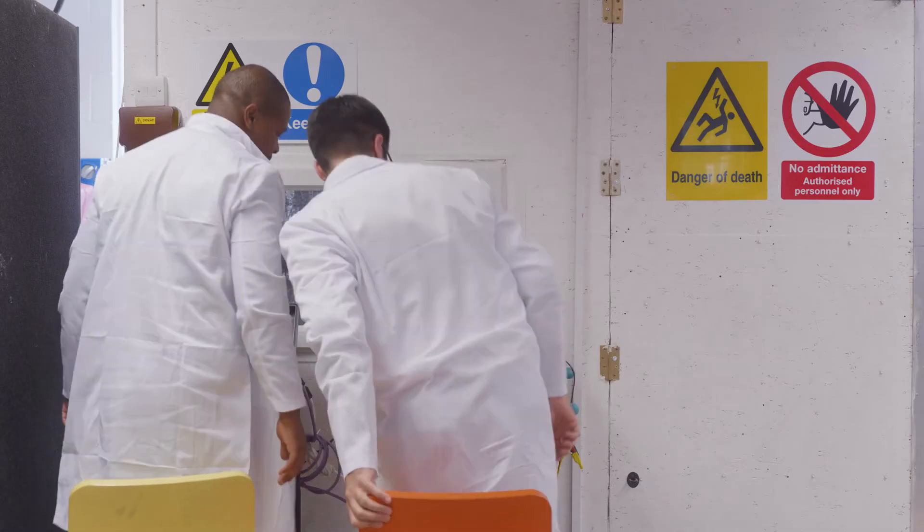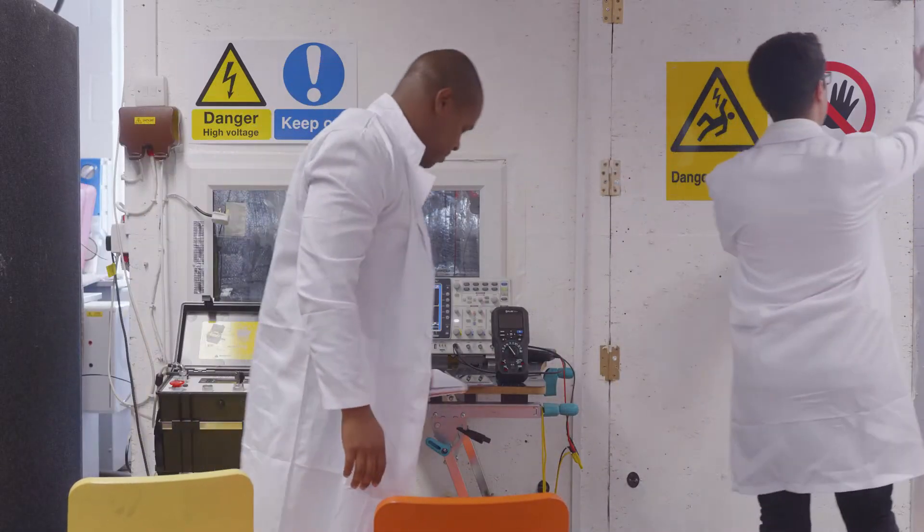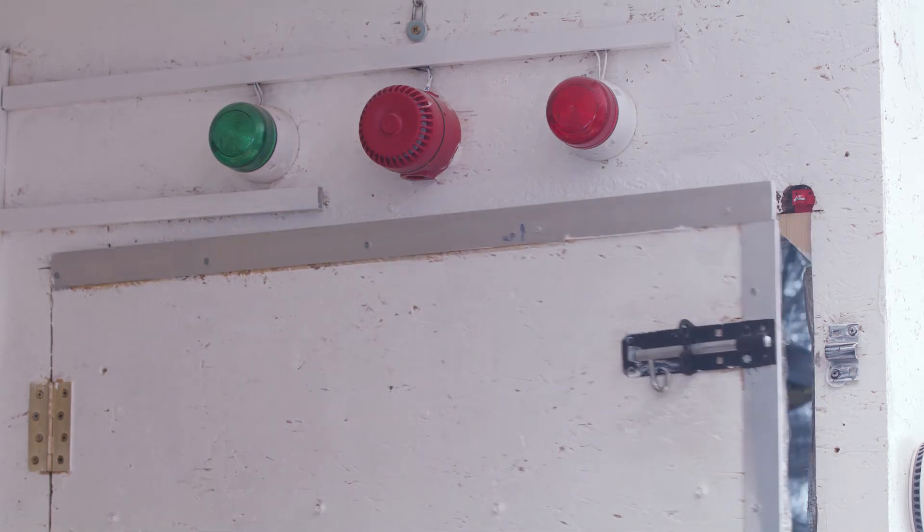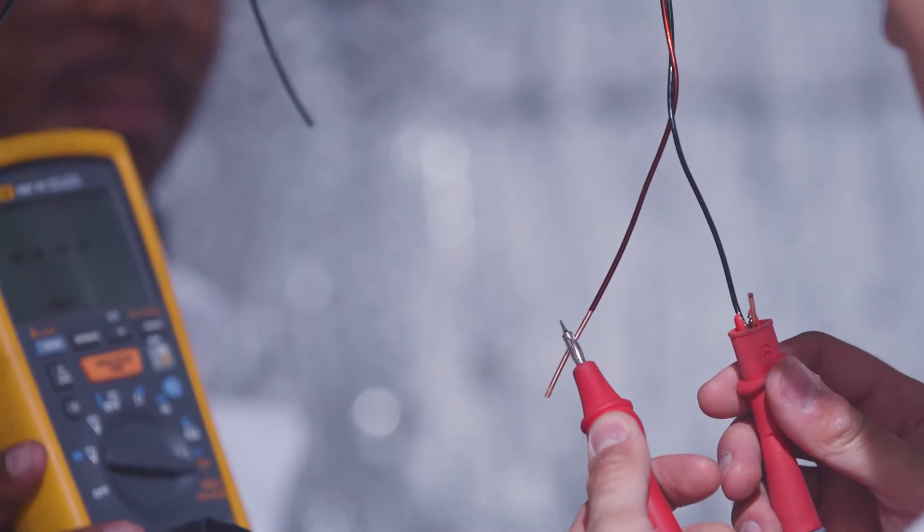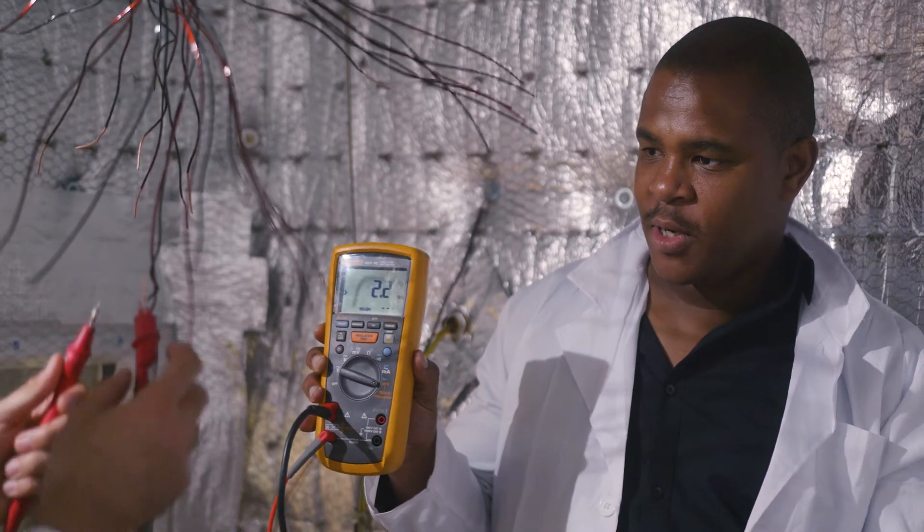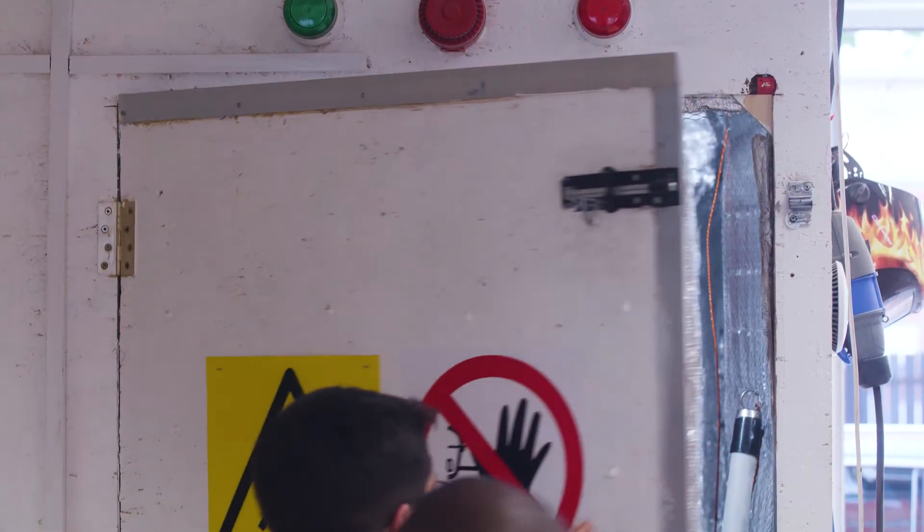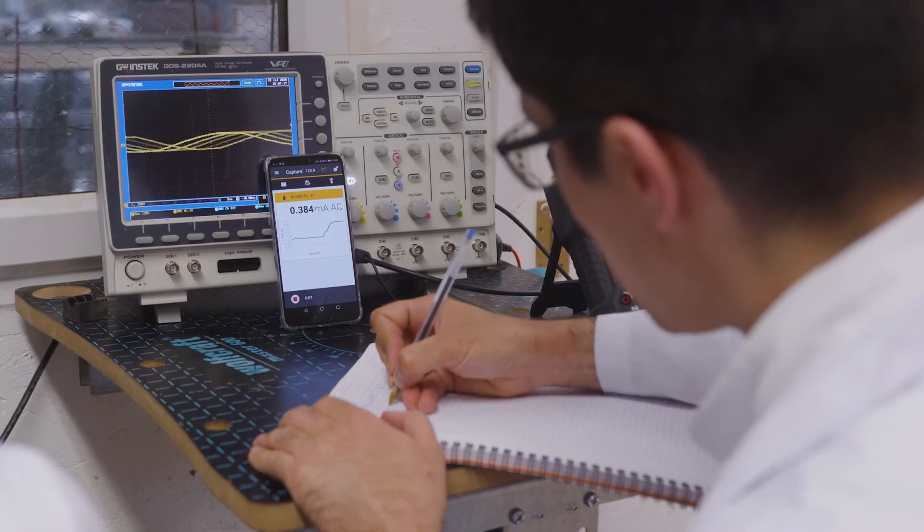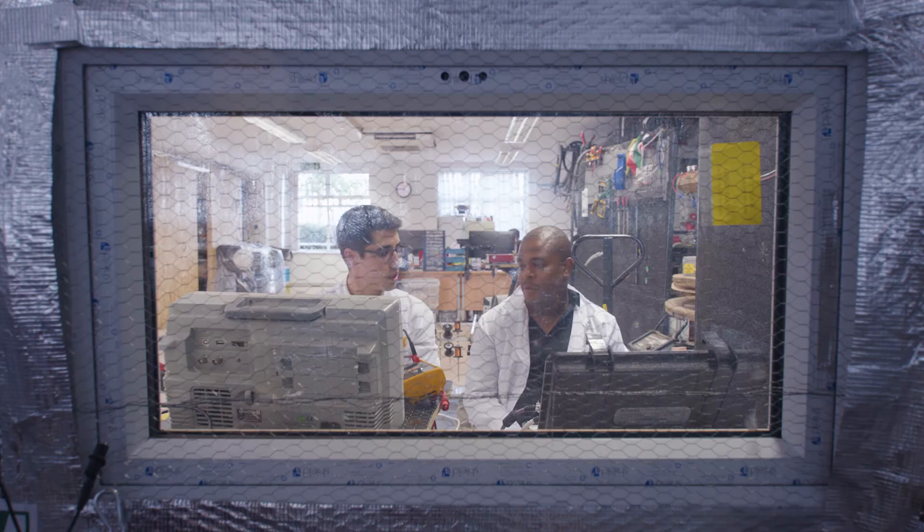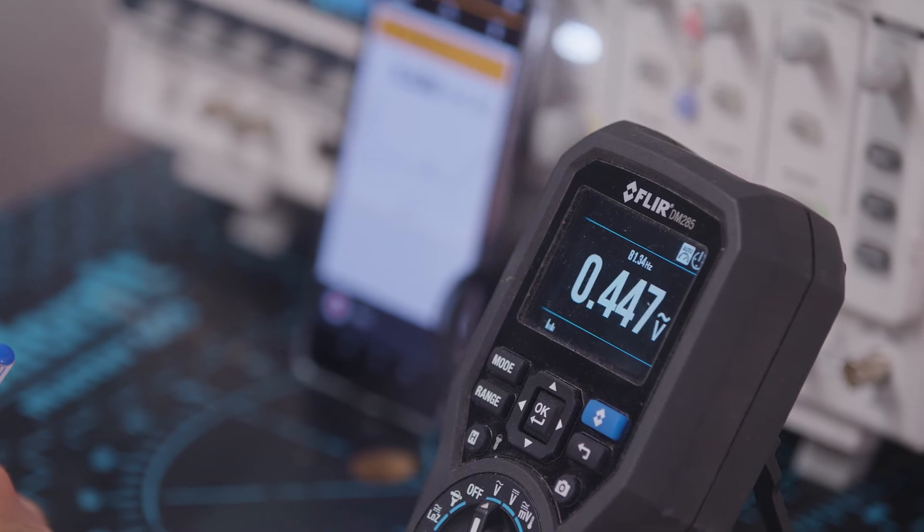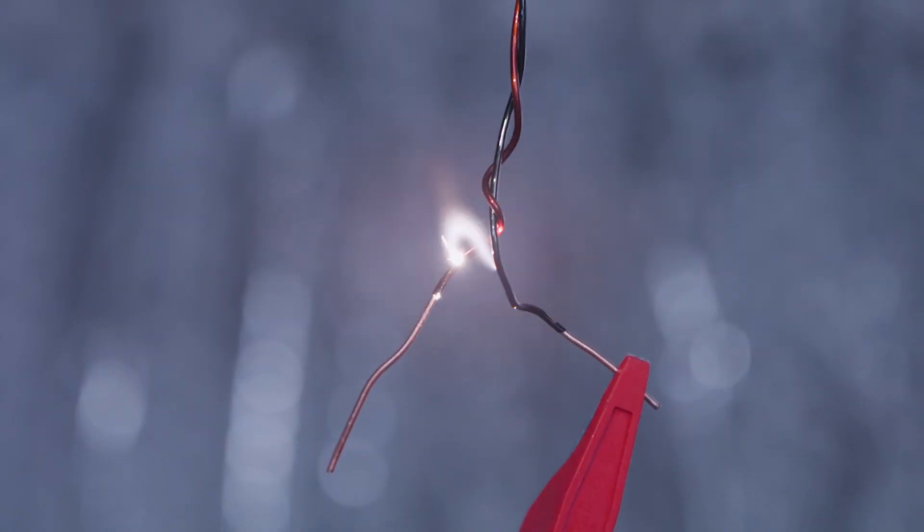There are two things that impede the flow of energy through a cable. One of them is resistance, which we can't do anything about. The other one is reactance. By balancing carefully the reactance with the capacitance which is in the cable, we remove one of the two impedances. We have reduced losses, and we have increased capacity. We can deliver more power through a given volume of copper or aluminum than you can with a conventional cable.